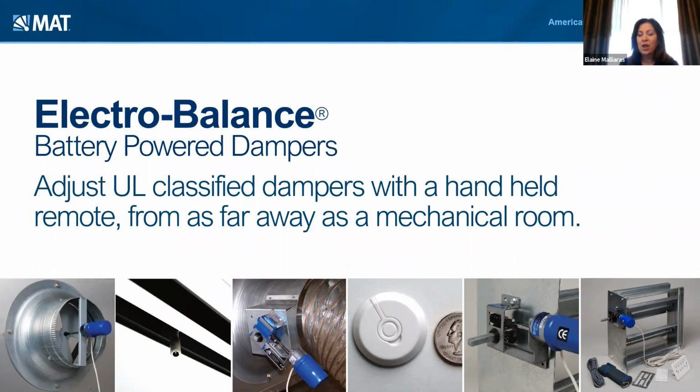battery operated. So here what we've done is, as I mentioned, we took our basic worm gear actuator that you're familiar with, we added the motor, we replaced the cable with plenum rated wire. So now you have no limitations in your cable runs, in your wire runs. You can go up to 1,000 feet, right? And this system is a very simple plug and play system. We can ship out a 15 or a 25-foot plenum rated wire. You get it out to the field, it's too long. We send you extensions and you just plug and play.